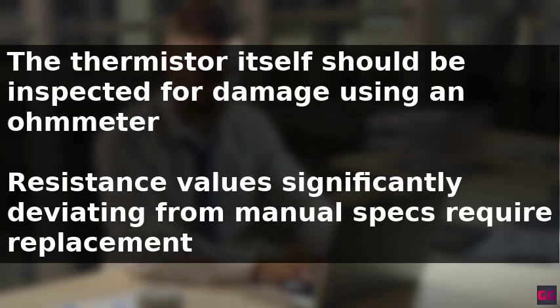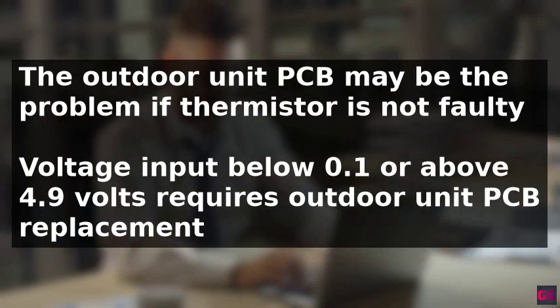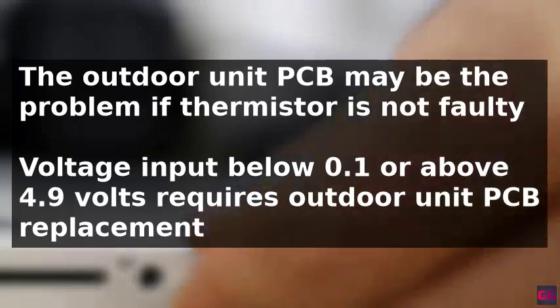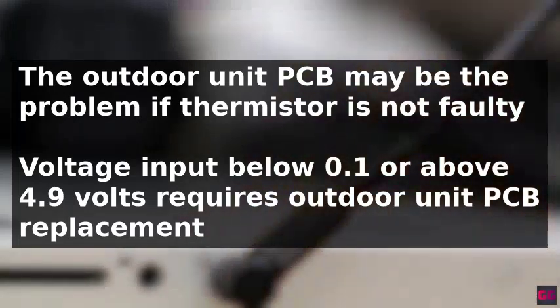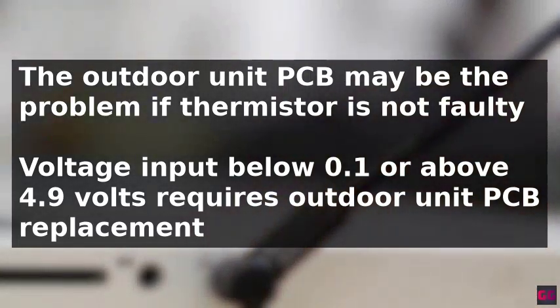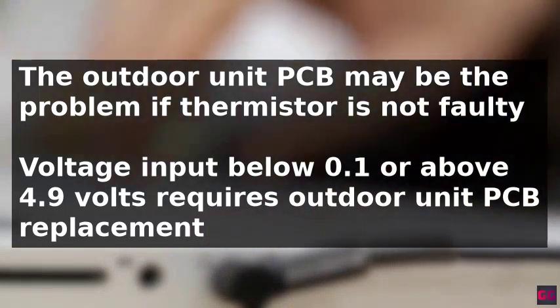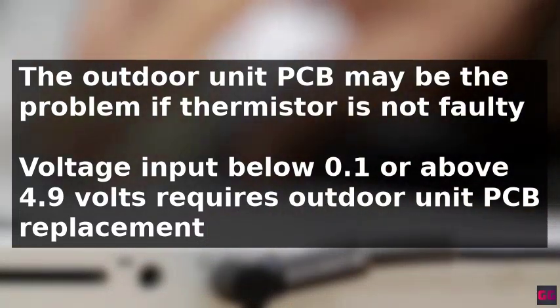In cases where the thermistor and its wiring are not faulty, the outdoor unit's PCB may be the problem. To verify this, the thermistor's voltage input should be measured when the system is on. If the voltage input is below 0.1 volts or above 4.9 volts, the outdoor unit PCB should be replaced.